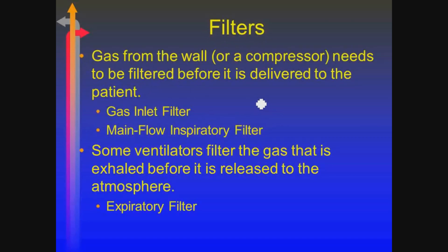Gas flow always has to be filtered prior to going to the patient. There's a couple different filters that you end up having. One, where the 50 psi line hooks up to the ventilator itself, where it screws on, and when you take a look at them, behind that, there's a small brass filter. We don't change them. We don't worry about them. Biomed takes care of that. But it's basically there to get large particulate matter that might be stuck inside the wall someplace.